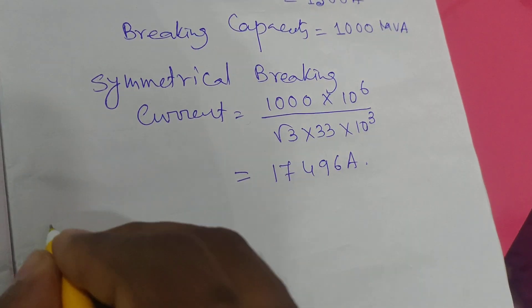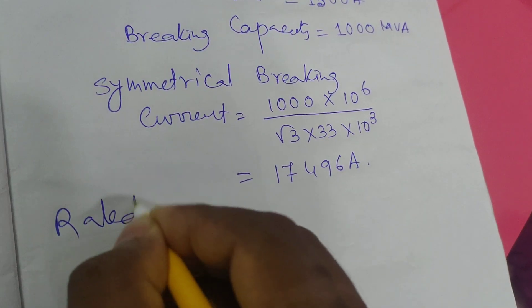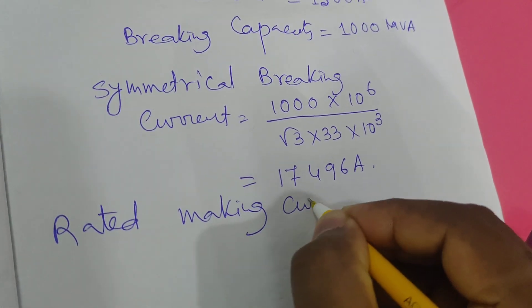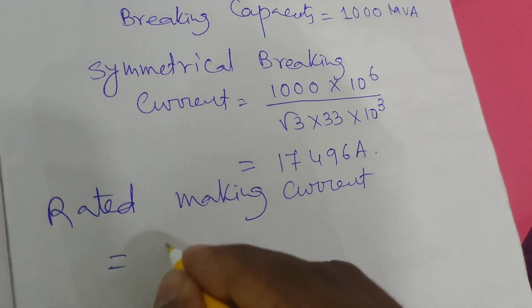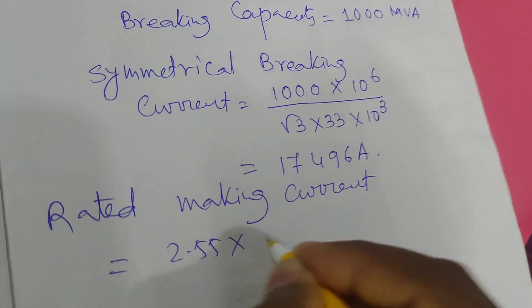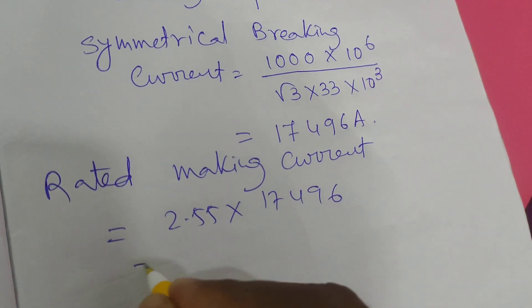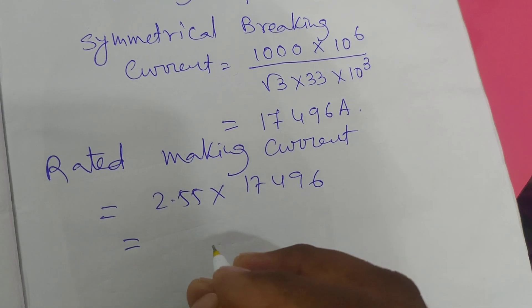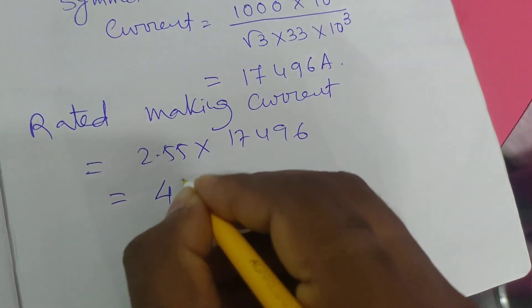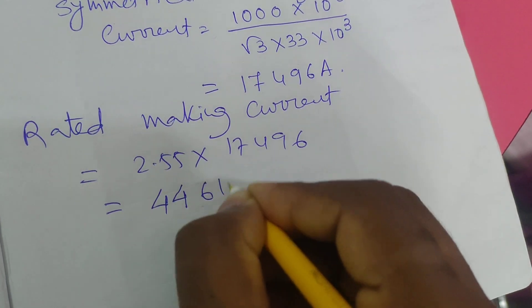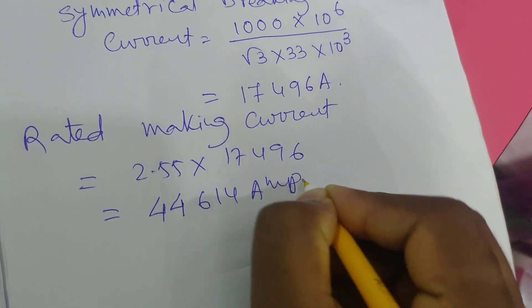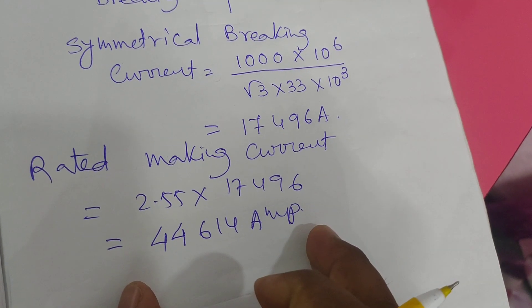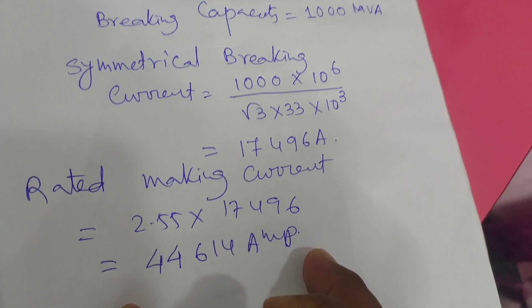The rated making current will be 2.55 × 17,496, which gives 44,614 ampere. This is the making current.